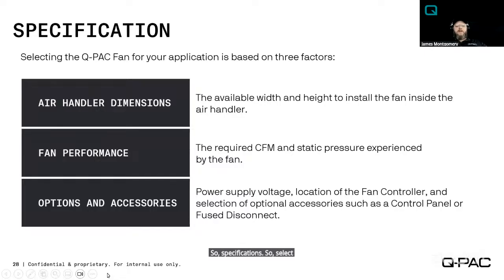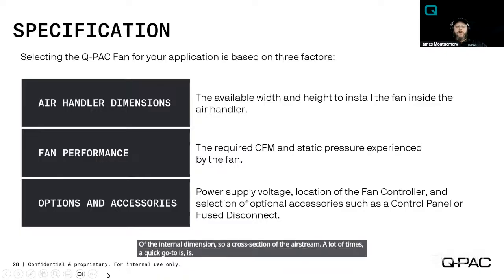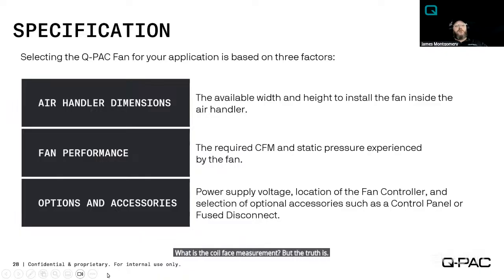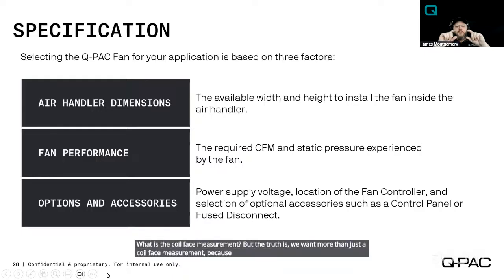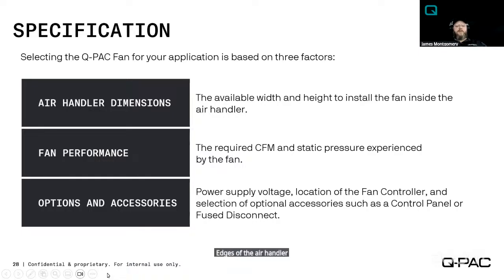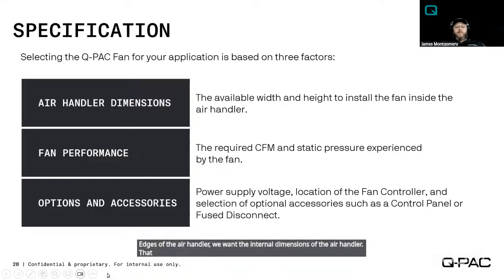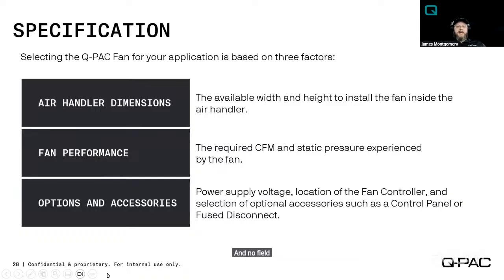So, specifications. Selecting the Q-PAC fan for your application is based on these three factors. What are your air handler dimensions? So we need to think height and width of the internal dimensions, so a cross section of the airstream. A lot of times, a quick go-to is: what is the coil face measurement? But the truth is, we want more than just a coil face measurement, because a coil face measurement doesn't extend all the way to the edges of the air handler. We want the internal dimensions of the air handler. That way, our fan frame can be designed to fill up that entire space, and no field modifications are needed.